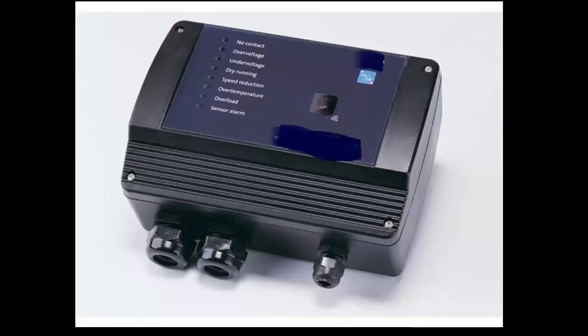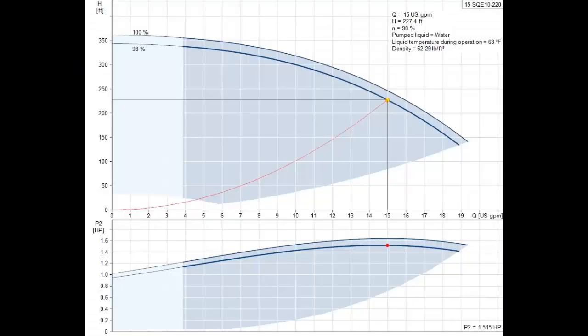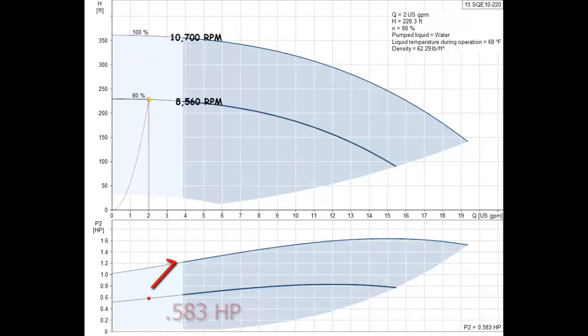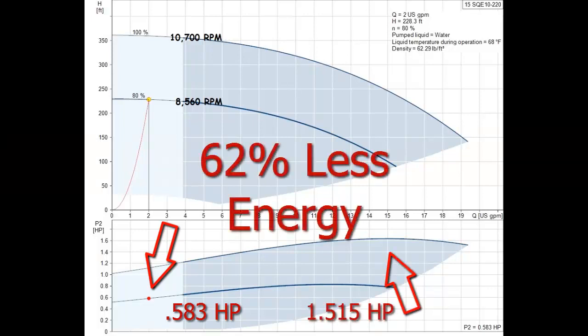A VFD causes the pump motor to be less efficient in several ways. In spite of these facts, many people will see the amp meter dropping from 1.515 horsepower at high flow and high RPM to 0.583 at low flow and low RPM and still say, look, the VFD is saving 62% in energy.